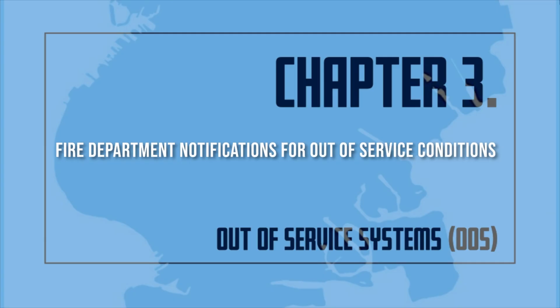9. The name and certificate number of the certificate of fitness holder responsible for supervision of the fire protection system that is out of service. When a certificate of fitness holder observes a major defect or out-of-service system, he or she shall report the defect to the borough dispatcher, the owner, and any responsible parties. When the certificate of fitness holder observes a minor defect or other condition not presenting a serious safety hazard, he or she shall report the defect or condition to the owner. If the defect or condition is not corrected within 30 days, it shall be deemed to be an impairment and reported in writing to the fire department.